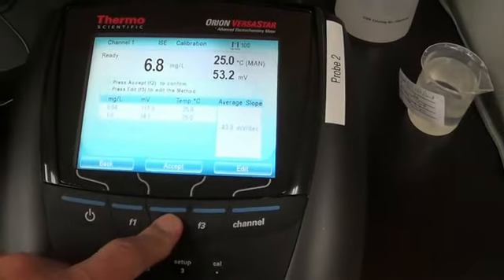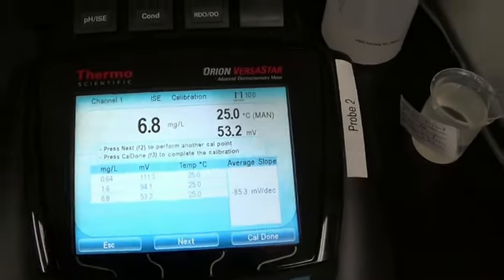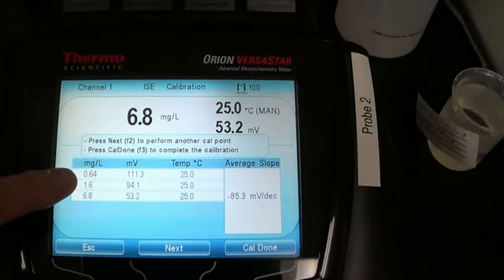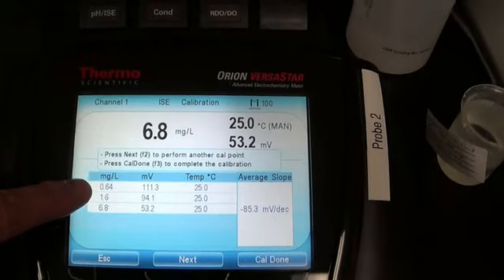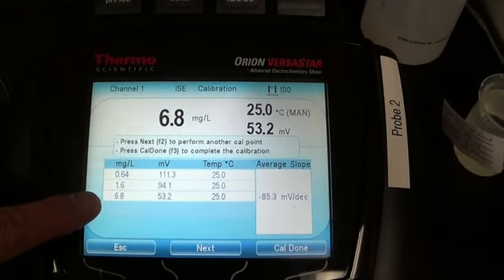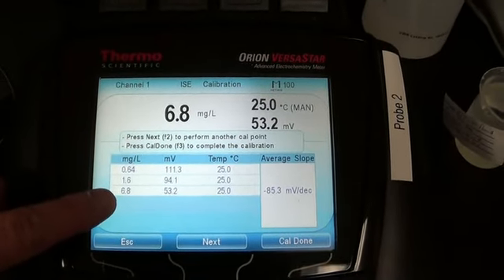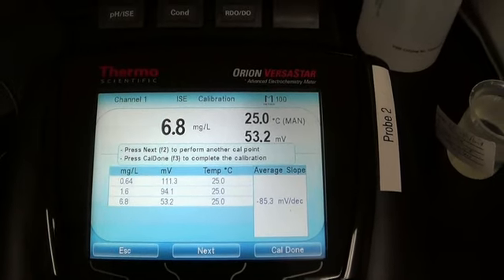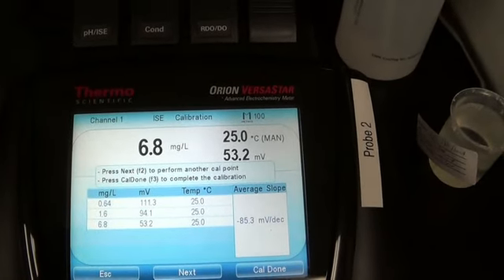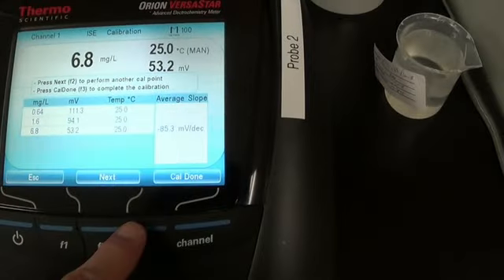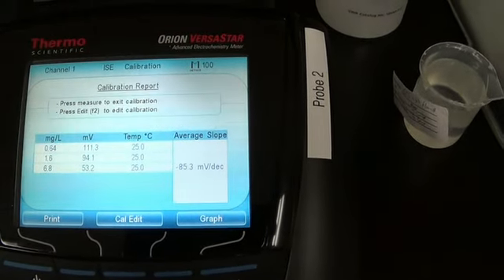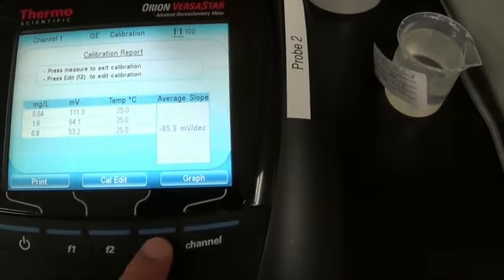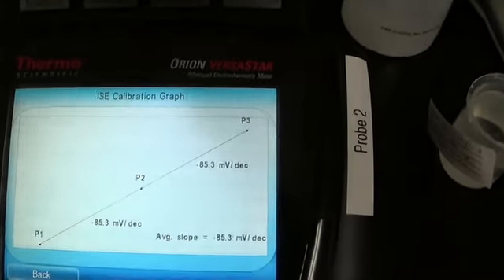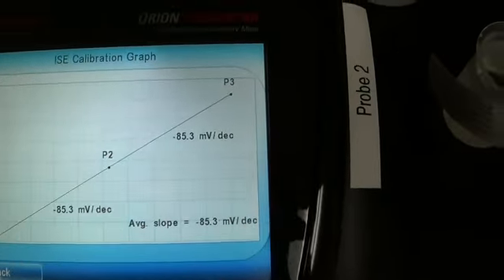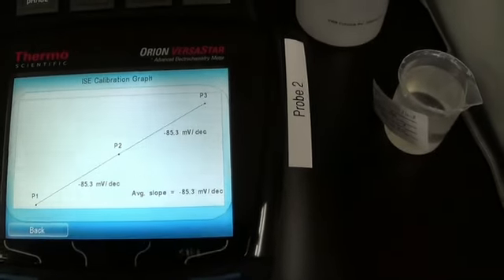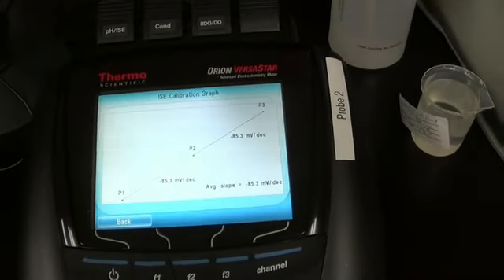I'm going to hit accept and take a look here. The 1 read 0.64, the 2 read 1.6, and the 10 read 6.8. So that's not unusual because you added 50 mils of the TISAB. So you can hit Cal Done. We can look at the graph if we like. Isn't that quite nice? Nice and linear. Now it's ready. You can do your test samples.